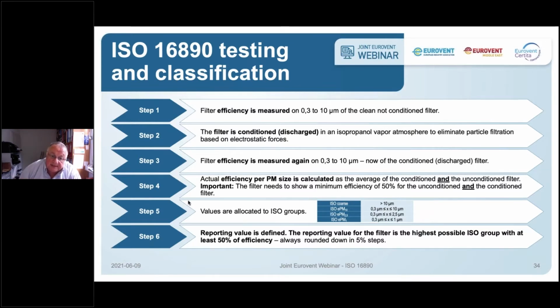The discharging is done by putting the filter in an isopropanol vapor atmosphere, which eliminates the electrostatic forces. Then we measure again the efficiency between 0.3 and 10 micrometers of the discharged filter, and that efficiency will be lower. In step 4, the efficiency of the new filter and the discharged filter is averaged—that's an important point—and that average is the efficiency of the filter. The filter needs to show a minimum efficiency of 50% for both the unconditioned and conditioned filter for the respective filter class, which I'll come to in a moment.